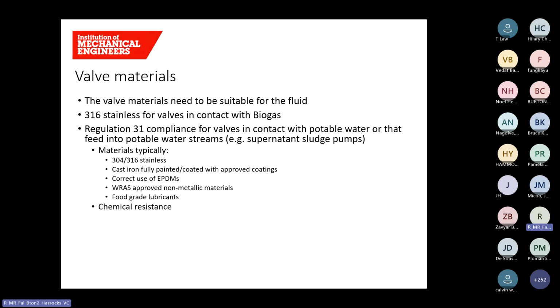Valve materials also play a part in valve selection. Some materials, such as plastics, have a limited pressure rating compared to the metallic alternatives. The fluid type, though, is the main factor when selecting materials. For example, chemical applications often need special resistant materials, or abrasive fluids can cause excessive wear, and so hard materials or surface finishes should be used.